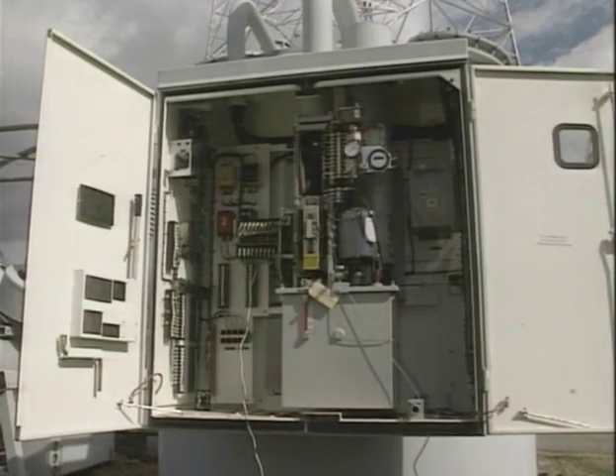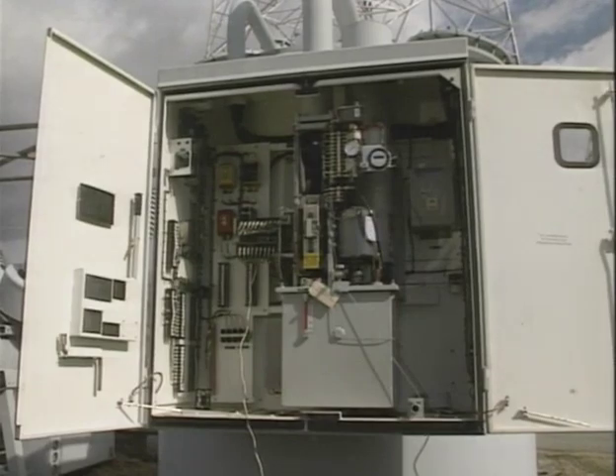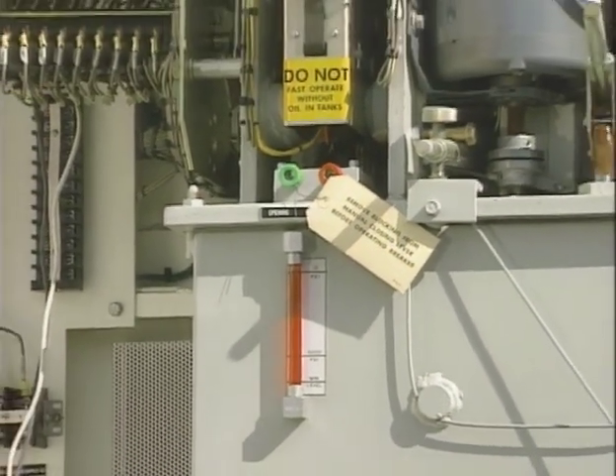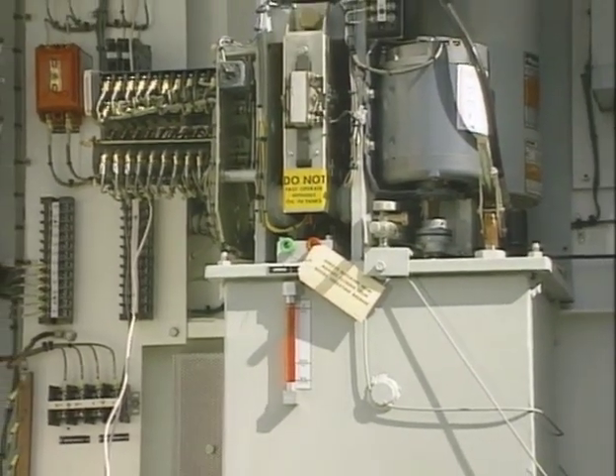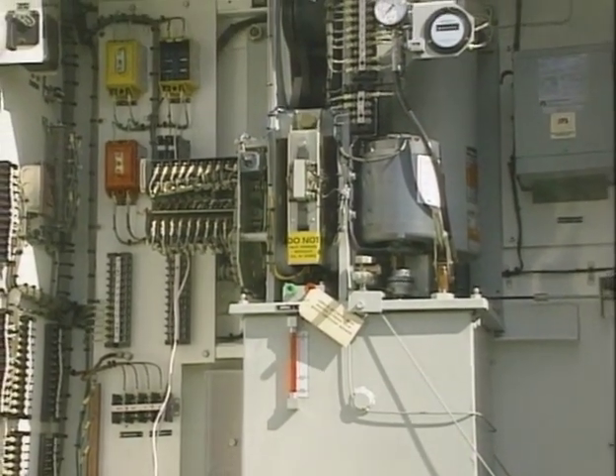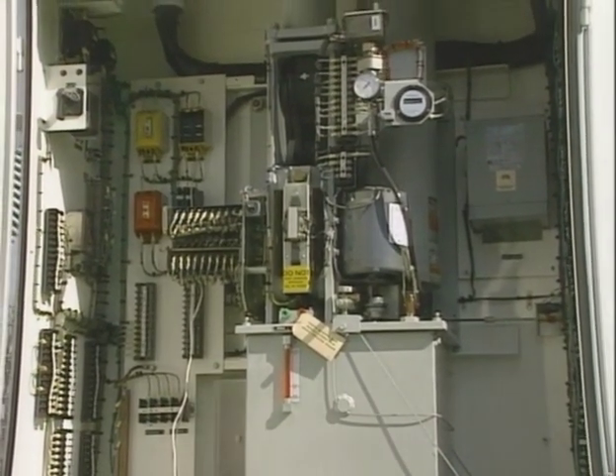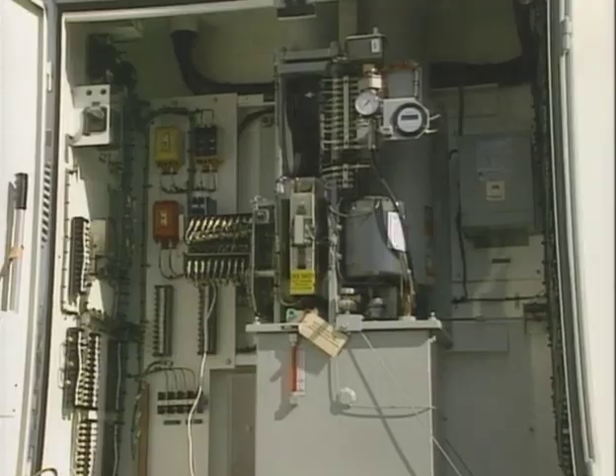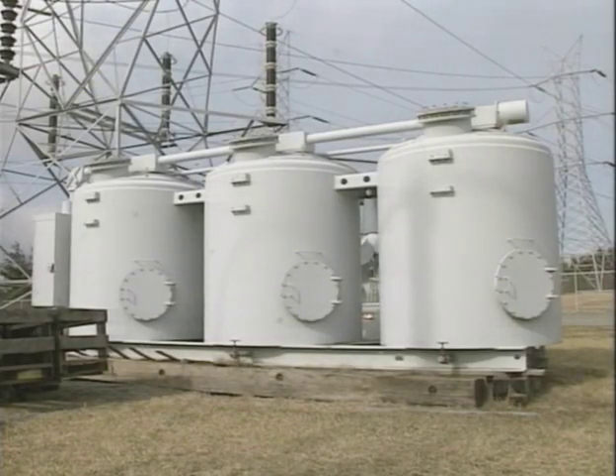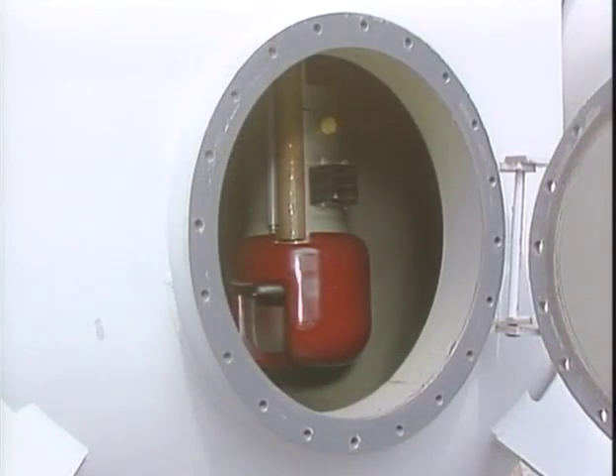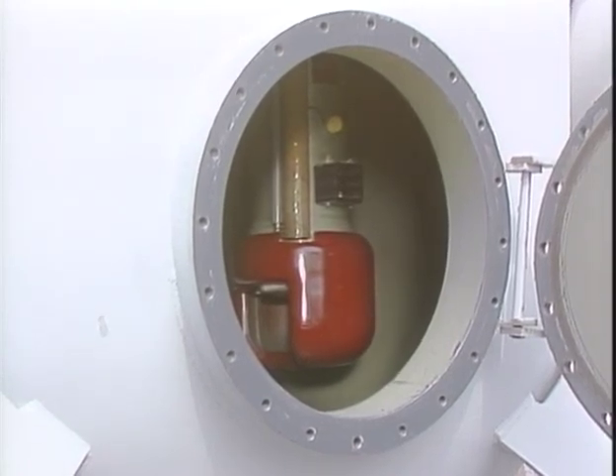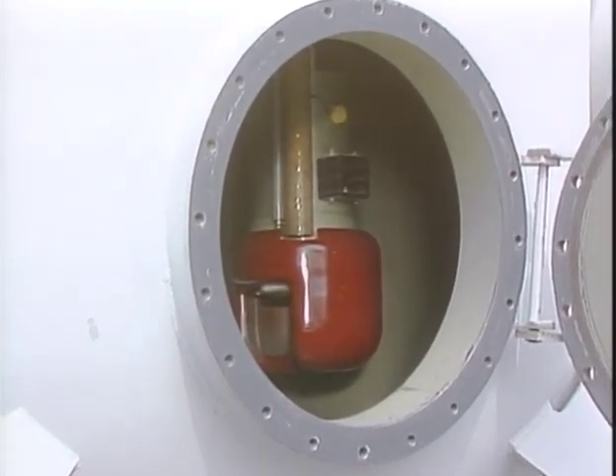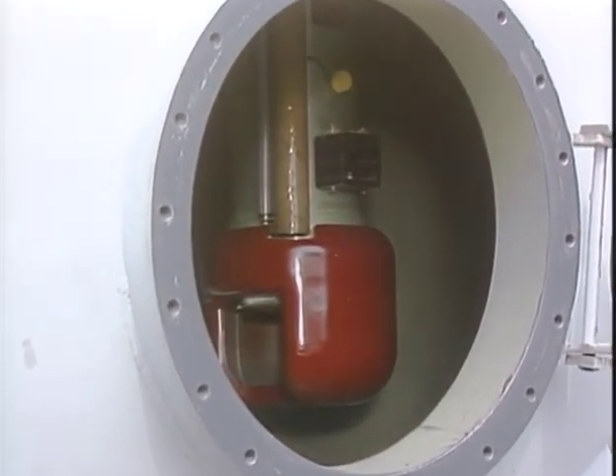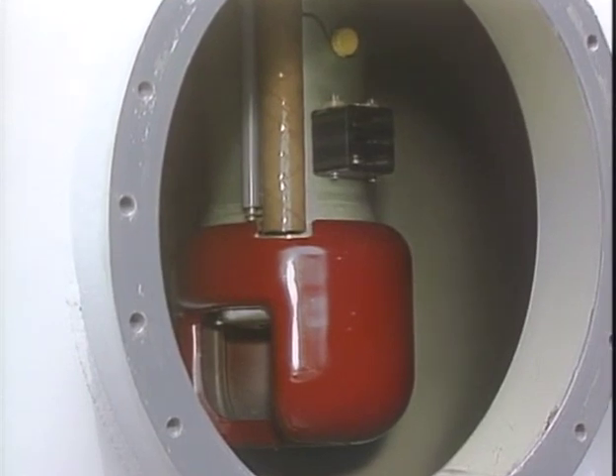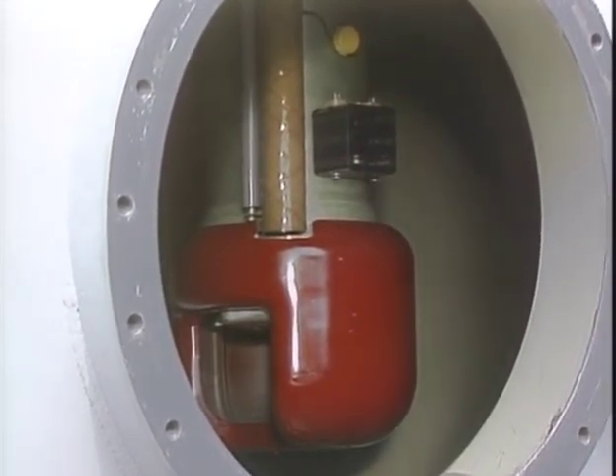The components inside the breaker operating mechanism cabinet are also inspected. Common problems include broken gauges, leaking fluid, cracked fuse boxes, and other obvious damage. Such damage may indicate that the breaker has been dropped, which could also result in damage inside the breaker. If a breaker is large enough to be entered, the components inside the tanks are thoroughly inspected for damage. Be sure to follow the proper safety precautions for entering a confined space. It's also important that moisture and dirt not get inside the breaker, so a breaker should not be opened if the weather is rainy, snowy, humid, or windy.